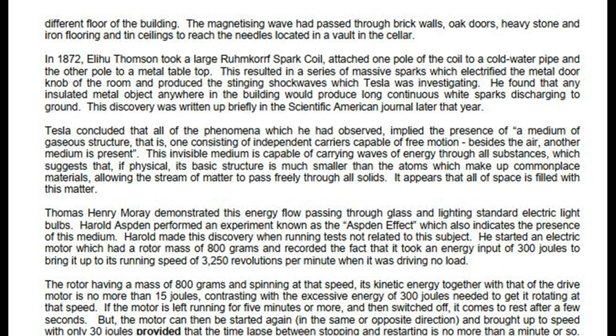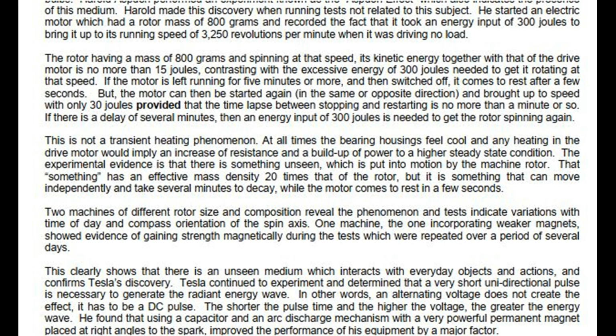If the motor is left running for 5 minutes or more and then switched off, it comes to rest after a few seconds. But the motor can then be started again, in the same or opposite direction, and brought up to speed with only 30 joules, provided the time lapse between stopping and restarting is no more than a minute or so. If there is a delay of several minutes, then an energy input of 300 joules is needed to get the rotor spinning again.